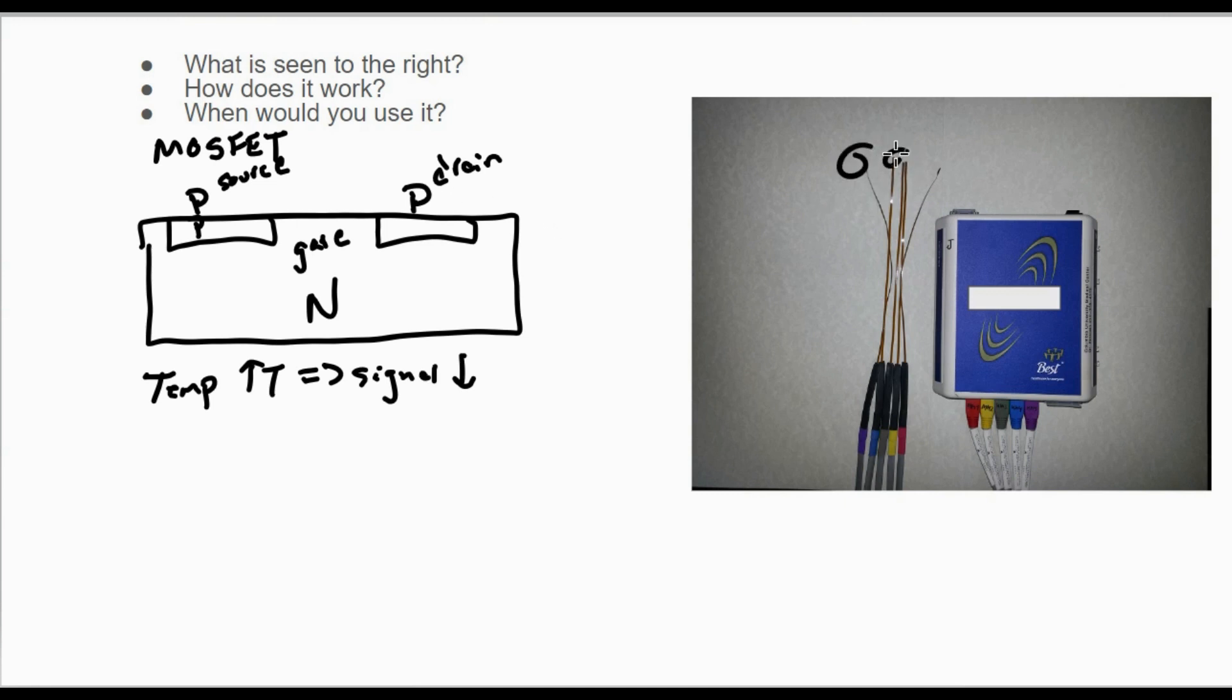You see over here we've got multiple different MOSFETs—those are all for different energies. They all have different channels, which you can see right here. Dose and dose rate can affect the readings. There is some fading, which is why you need to do your monthly calibrations.